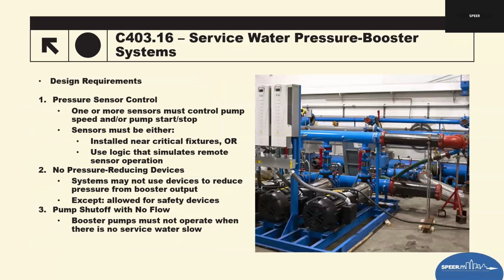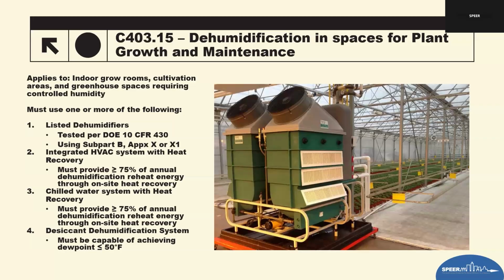Plan reviewer. Plan review: confirm whether the space qualifies for an indoor grow or greenhouse area. Verify that one of the four compliance pathways is used in the design. Check for DOE 10 certification if those packaged dehumidifiers are being used. For heat recovery systems, require the annual energy calculation showing greater than or equal to 75% reheat contribution. And then field inspection tips. Verify the installed equipment matches the approved submittals. Confirm that the heat recovery components are installed and connected.